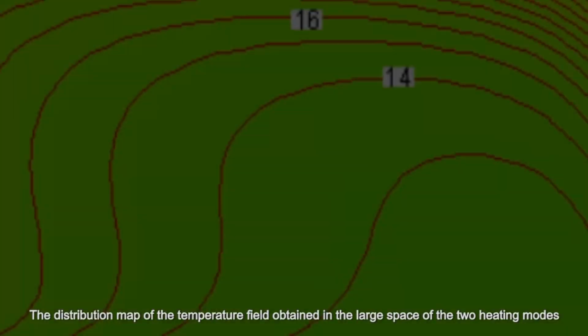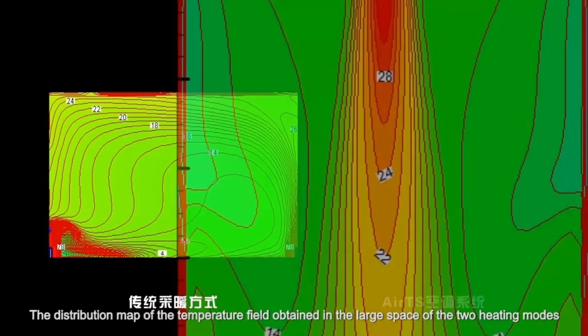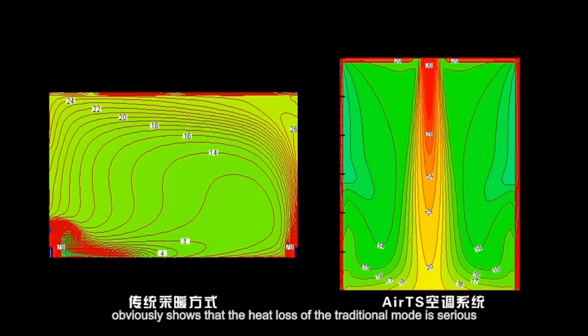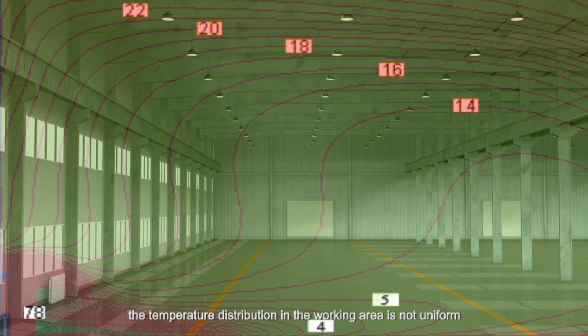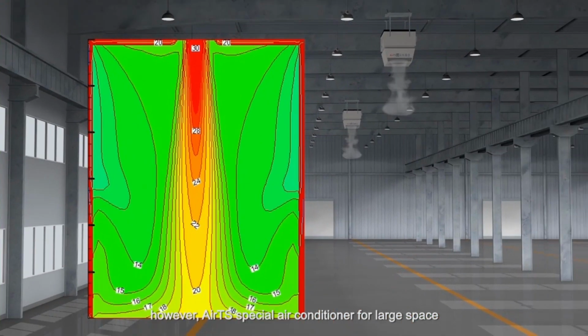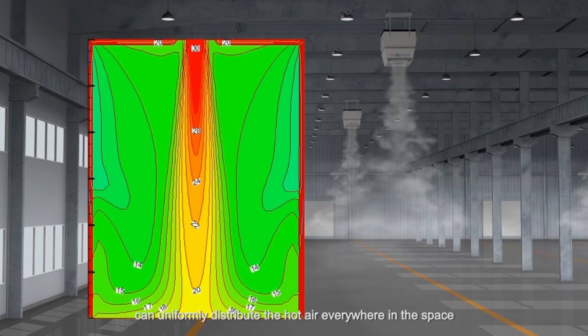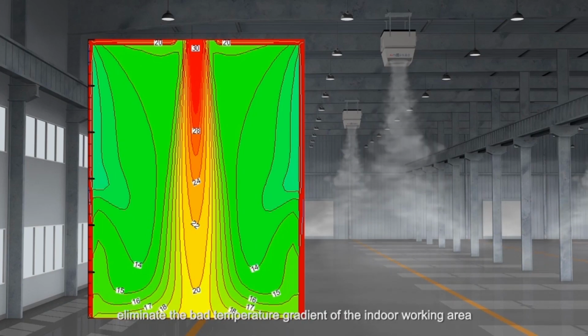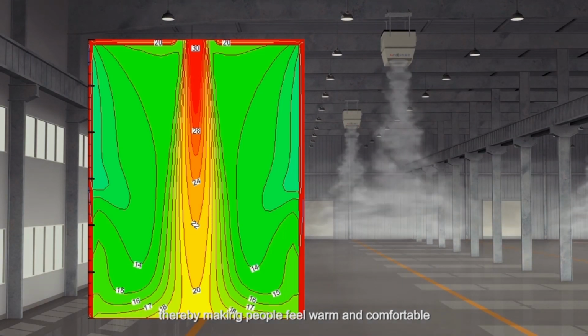The distribution map of the temperature field obtained in the large space of the two heating modes obviously shows that the heat loss of the traditional mode is serious. The heat mainly gathers at the top space. The temperature distribution in the working area is not uniform. However, AirTS special air conditioner for large space can uniformly distribute the hot air everywhere in the space, eliminate the bad temperature gradient of the indoor working area, thereby making people feel warm and comfortable.